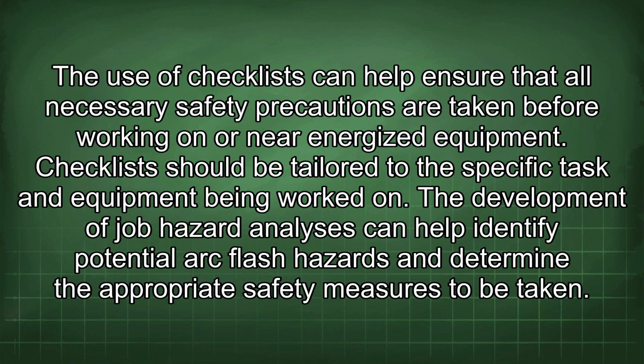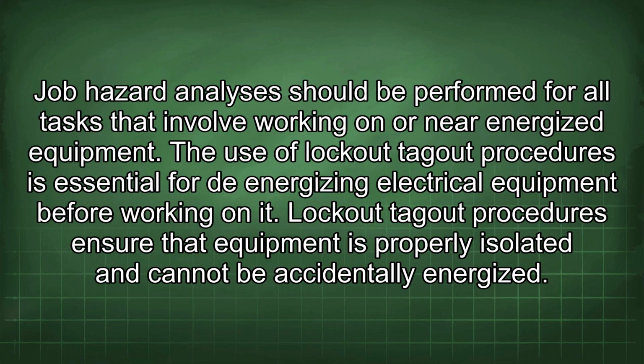The development of job hazard analyses can help identify potential arc flash hazards and determine the appropriate safety measures to be taken. Job hazard analyses should be performed for all tasks that involve working on or near energized equipment. The use of lockout-tagout procedures is essential for de-energizing electrical equipment before working on it. Lockout-tagout procedures ensure that equipment is properly isolated and cannot be accidentally energized.